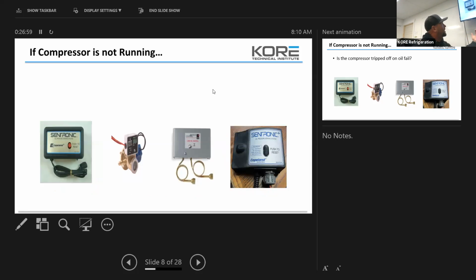Okay. Here's a couple other controls. A lot of these you'll see on bigger systems, bigger single systems, like your Senfronic, that's a Copeland control. So that's how they do their oil fail control. This is where I'm going to talk about button pushing. If you guys come up on an oil fail control situation and you hit the red button and call it a day, you're coming back. Or somebody's coming back behind you, and when they find out that you hit the red button and just walked away, they're not going to be too happy with you.